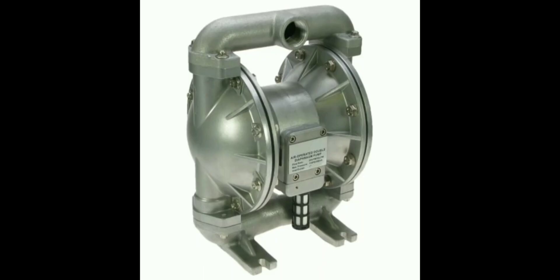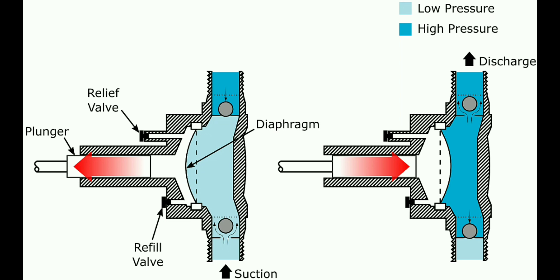Let us look at the advantages of a diaphragm pump. It is suitable for handling a wide range of fluids including corrosive and viscous substances. It is capable of self-priming, allowing it to lift fluid from a lower level to a higher level. It is well suited for applications requiring accurate metering and dosing. The diaphragm acts as a seal, eliminating the need for additional seals or glands.